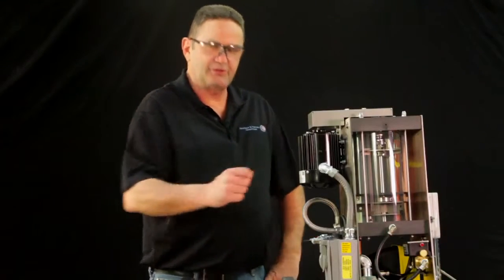Next phase we're going to hit on is common troubleshooting. A lot of the conditions that we're seeing out there, that our in-house technical support and I have taken phone calls on, are usually pretty easy fixes, very common. First one is, I have no water flow. Easiest conditions are, boom, is your unit plugged in? Is the solenoid energized? Two, is the water shut off someplace in your plant? Three, is your discharge shut off somewhere in the facility?